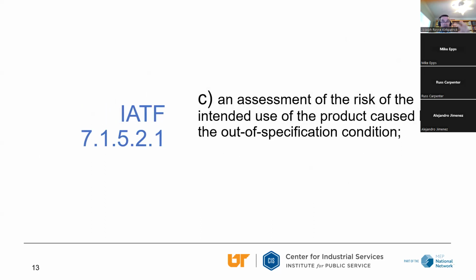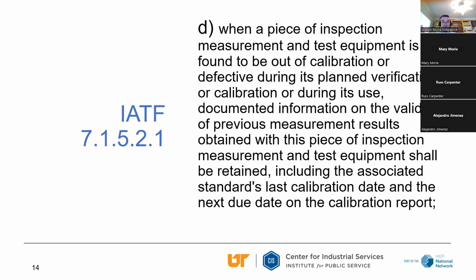IATF says you have to do an assessment of the risk of intended use of the product caused by the out-of-spec condition. And IATF also says when a piece of equipment is found to be out of calibration, you have to document the validity of previous measurement results, and you have to keep a record of this.